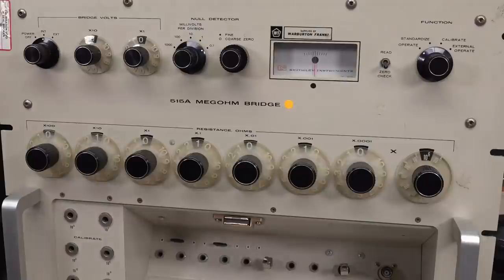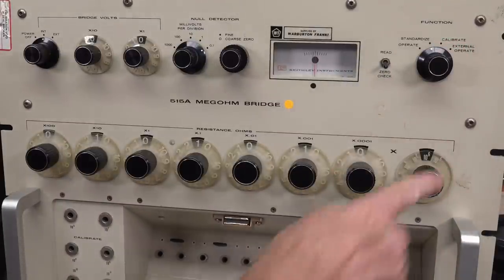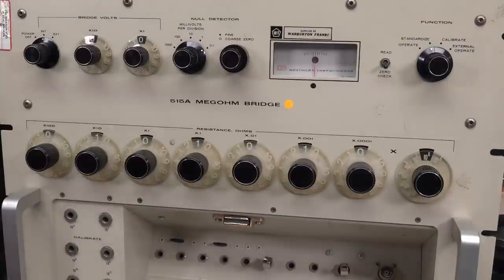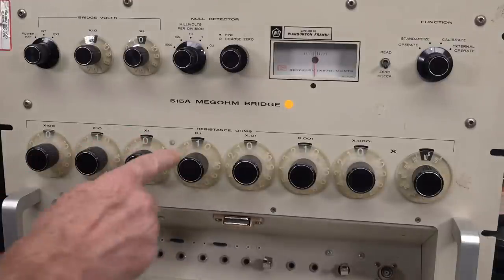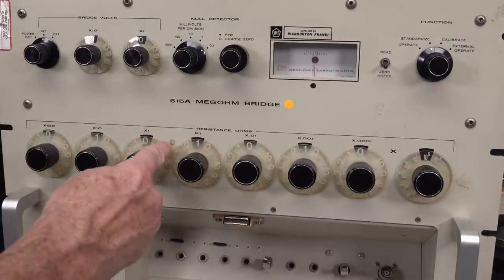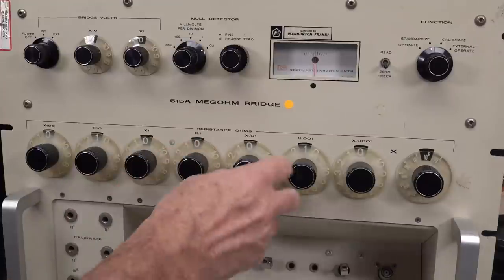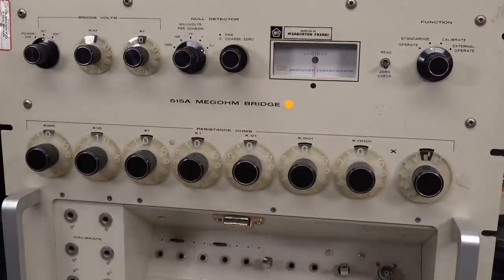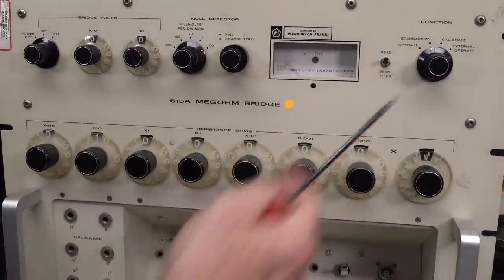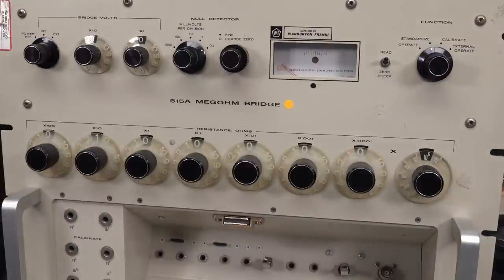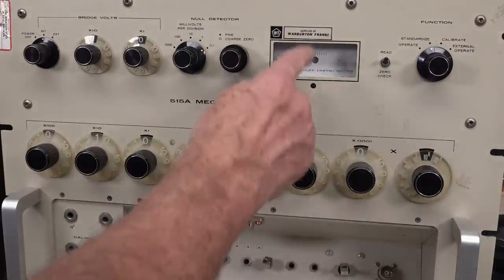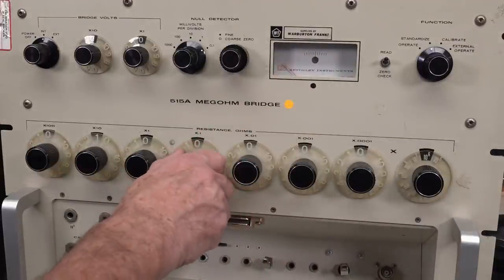Standardizing. So set function switch to standardize. And then multiplier to ten to the sixth. And then set it to exactly ten point, which is what that is. I assume that's supposed to light up. But yeah, there we go. Ten point zero zero. And we'll set that to read position.